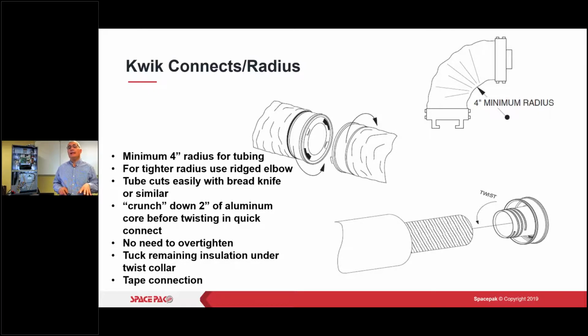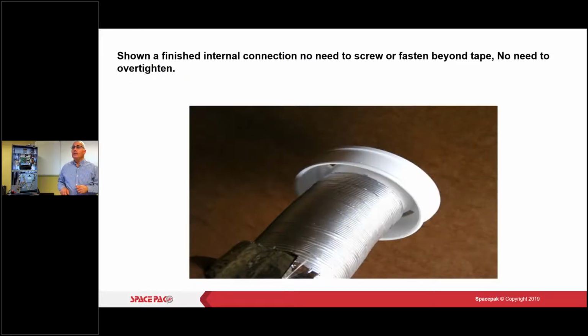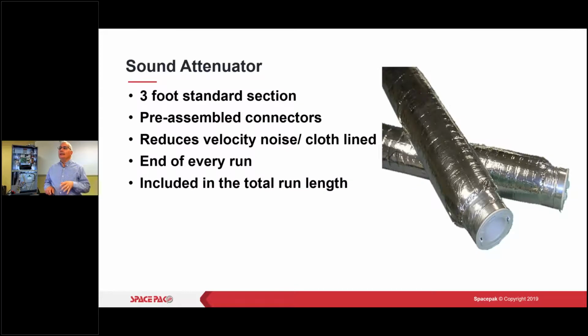We do have pre-made 90-degree elbows. So if I'm coming down a wall and I need to come out, I don't have to worry about bending or kinking the tubing. We do have pre-made elbows with a quick connect on either side, so you can snap it to your tubing and then have your outlet snapped on the other side. Okay. So you give it a little screw and you put it in there, a little turn, right? Don't overtighten it, then pull the insulation down and tuck it in, right? You must finish each 2-inch drop with the 3-foot sound attenuating tubing. It must be there. It's going to reduce noise dramatically, make for a nice quiet system. It has to be there, and this is included in that total length of run.